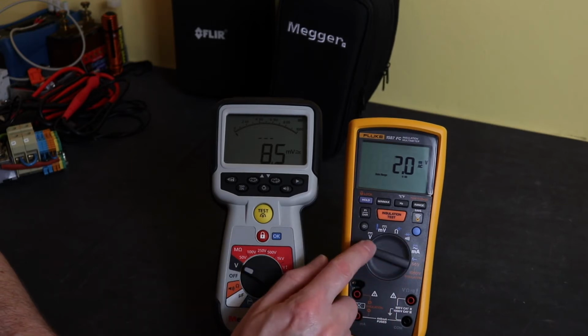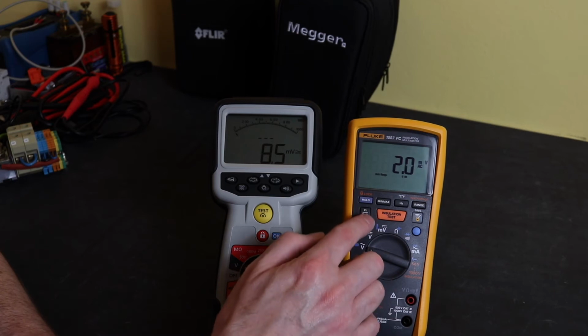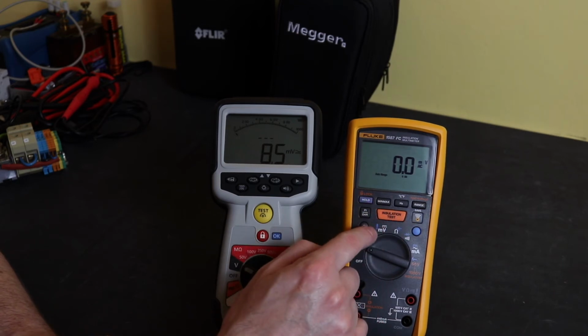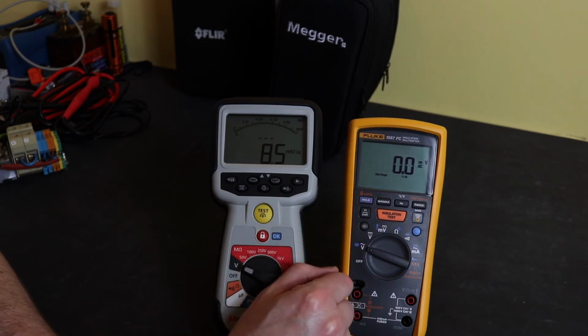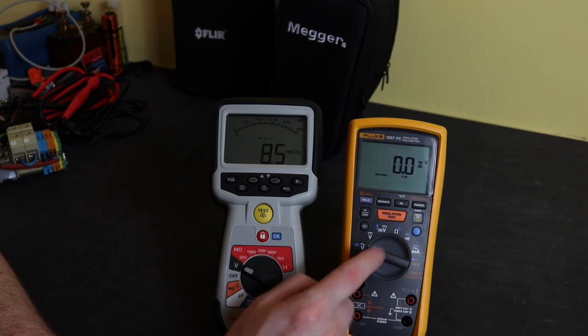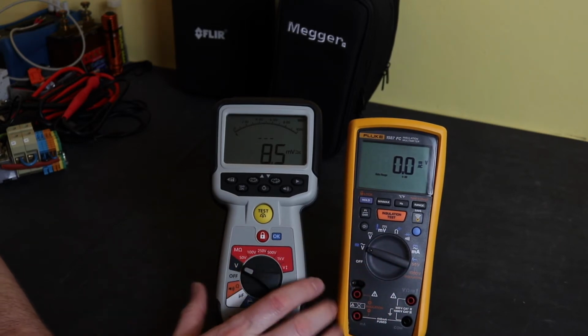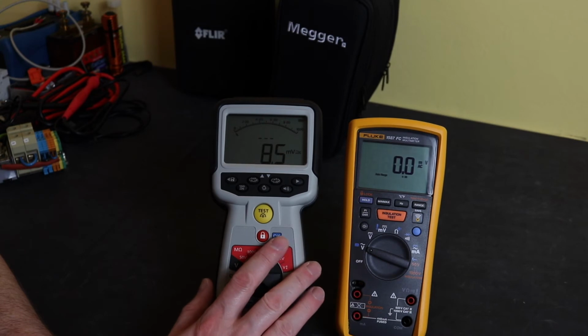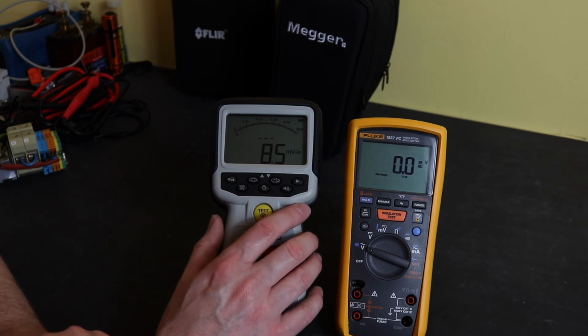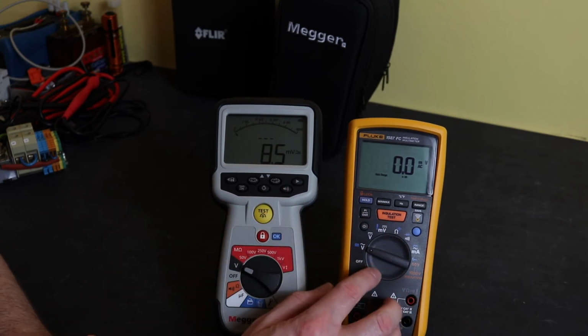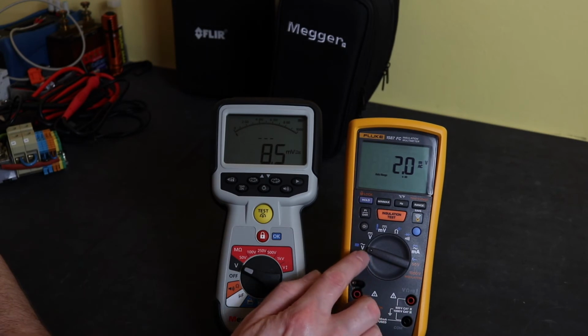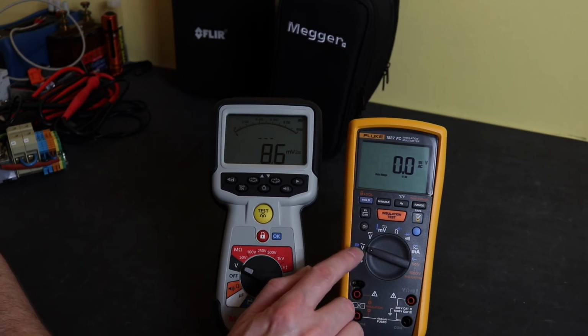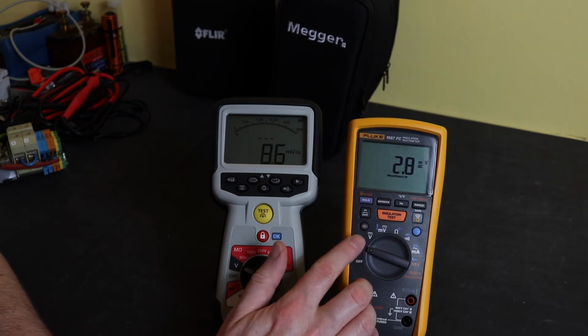Rotary switch to get to the main functions, and then sub-functions are off of these menu buttons underneath the screen here. First position on both the instruments is voltage. The Megger defaults to AC DC mode. The Fluke doesn't have an AC DC mode. It goes straight to AC mode, and you also have a low pass filter available in this mode as well.